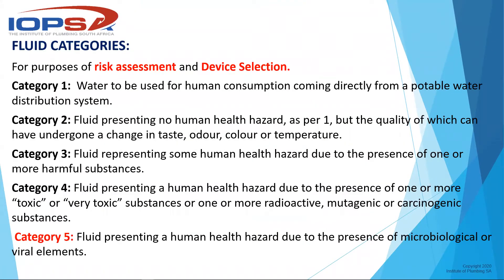For risk assessment purposes, water has been broken into five categories. Category one is water used for human consumption coming directly from a potable water distribution system - your normal municipal water. Category two is fluid presenting no human health hazard but whose quality may have undergone a change in taste, odor, color, or temperature. This would include water softeners on your line, or heated water from a geyser, meaning most houses fall into category two.